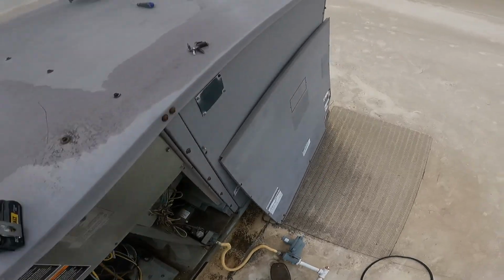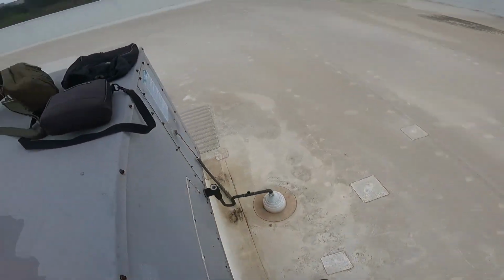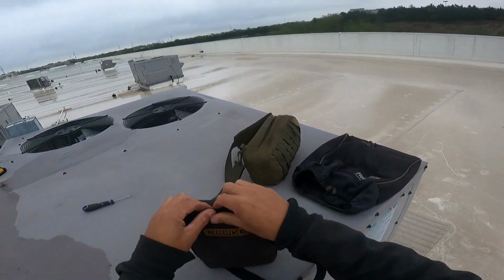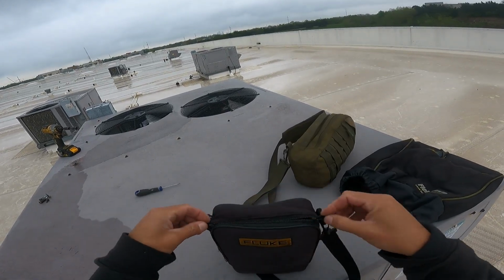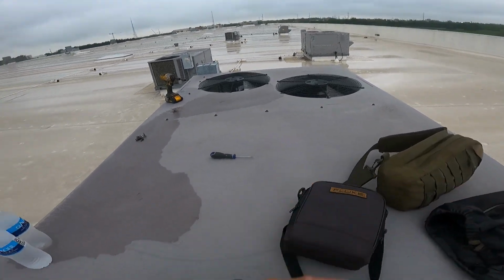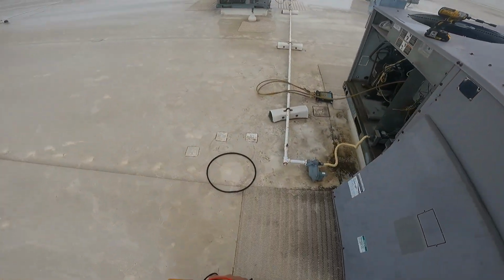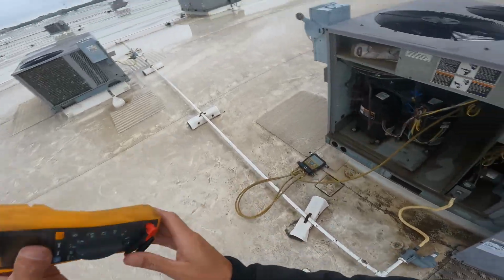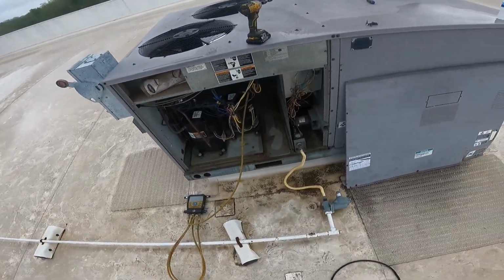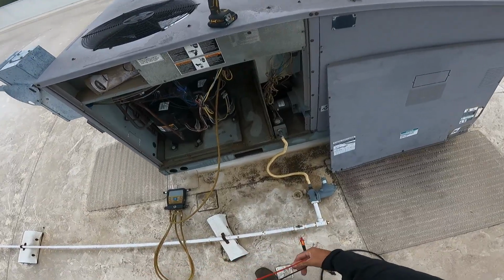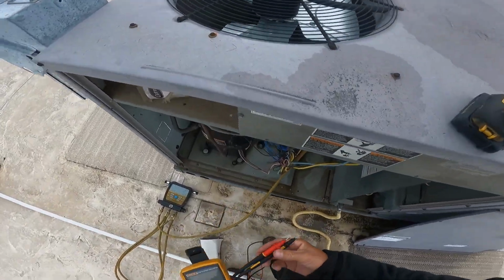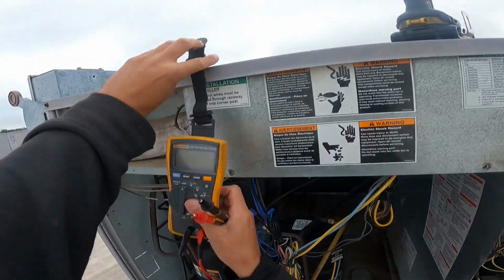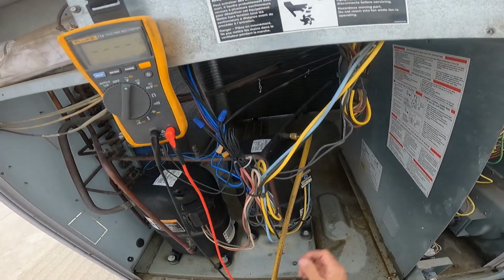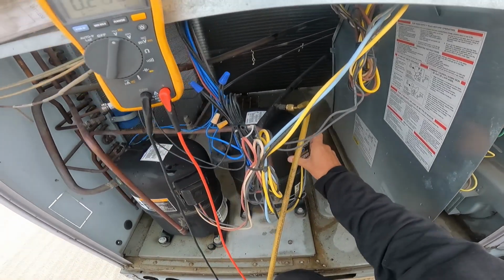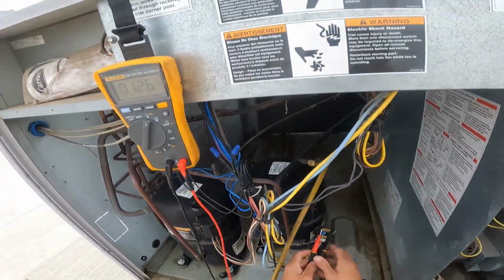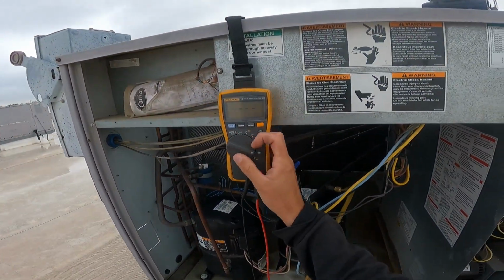Most likely, not 100%. I'm going to check the windings on these too. A circuit flat on charge could be a Schrader valve or an evaporator leak. I don't know where the leak is yet, so we're going to look for signs, like oil, because that usually shows where these leaks are.